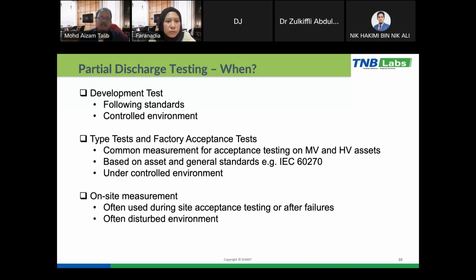And then, of course, after the installation of the equipment at site, we can do the partial discharge testing as a commissioning, as an acceptance test, or even after the failure, we can do the partial discharge testing to determine whether there is a possibility that partial discharge has occurred in the equipment. So on the development test, normally it follows the standards. There is a guideline governed by the IEC for transformer, cable, and switchgear. And also normally we do it in a controlled environment. So there is no noise.